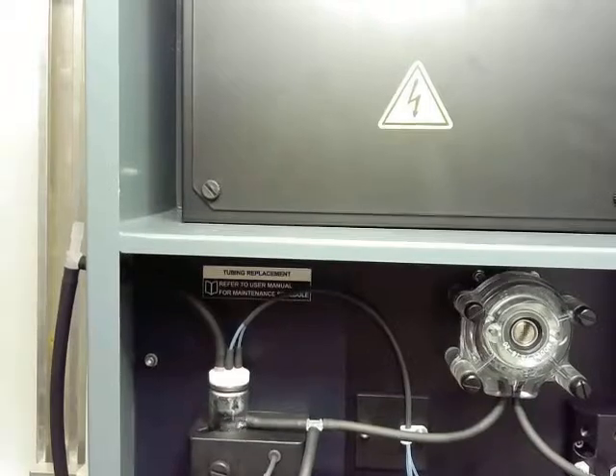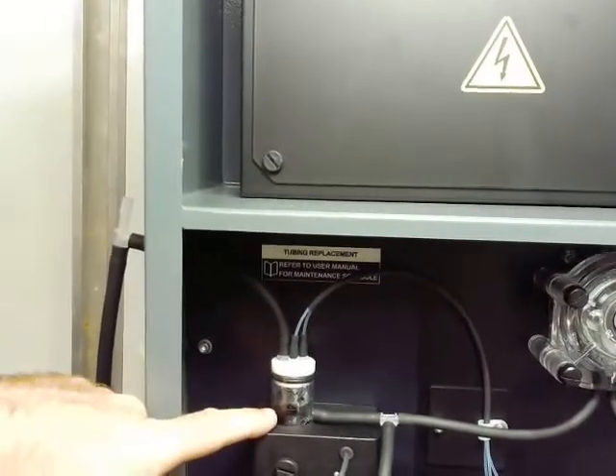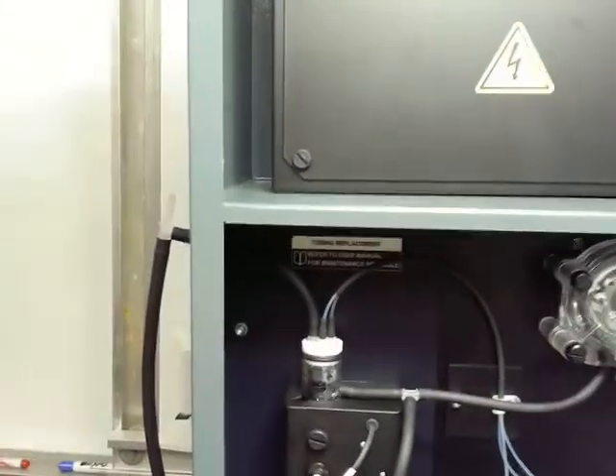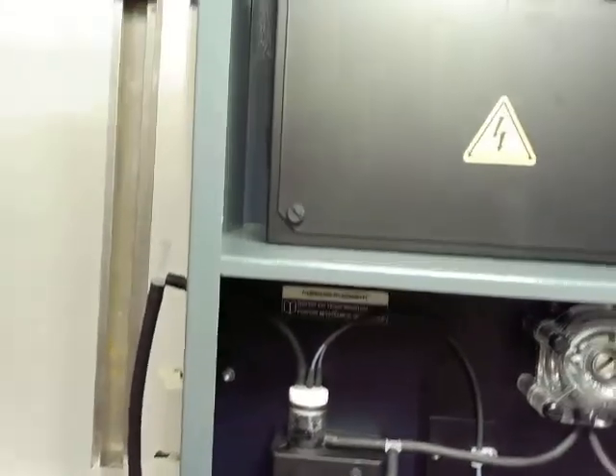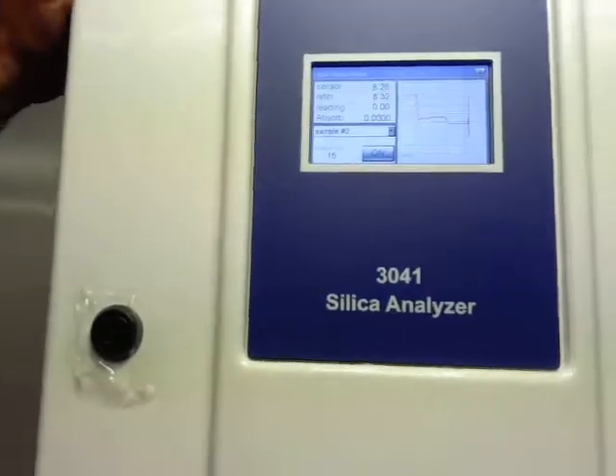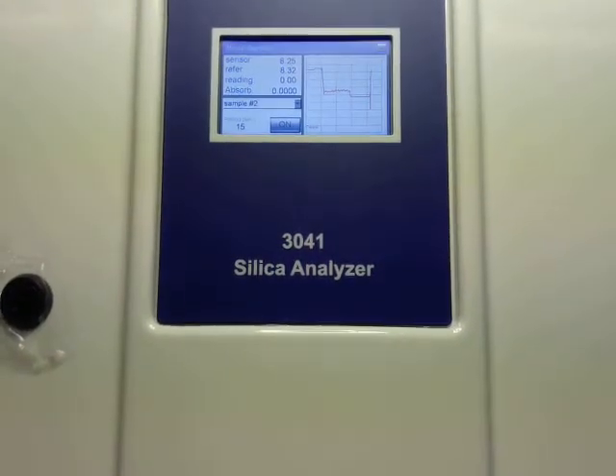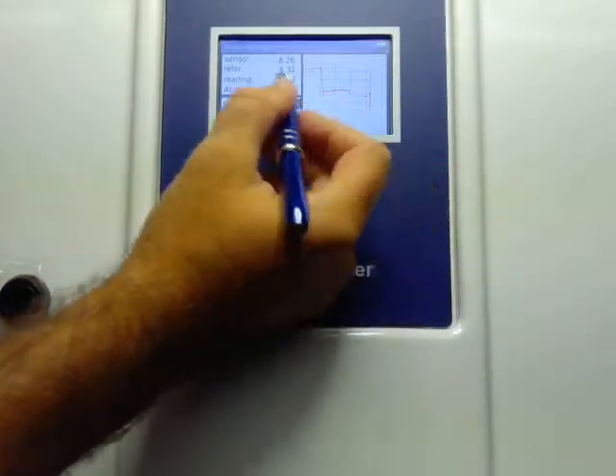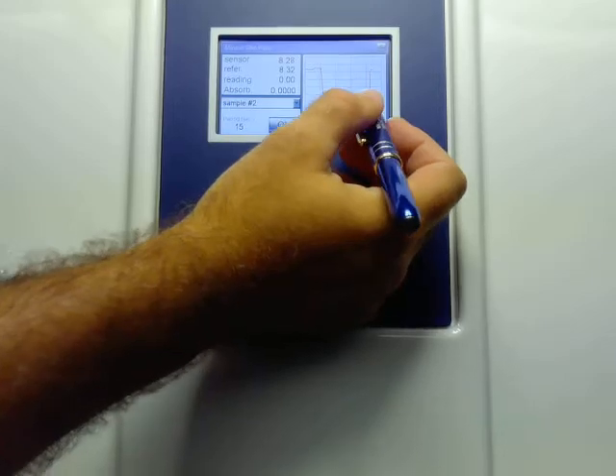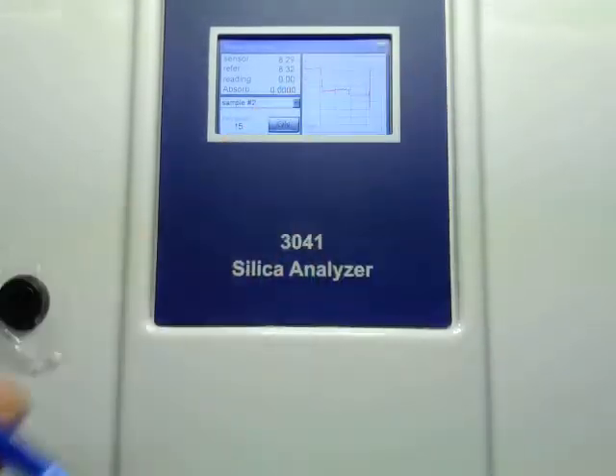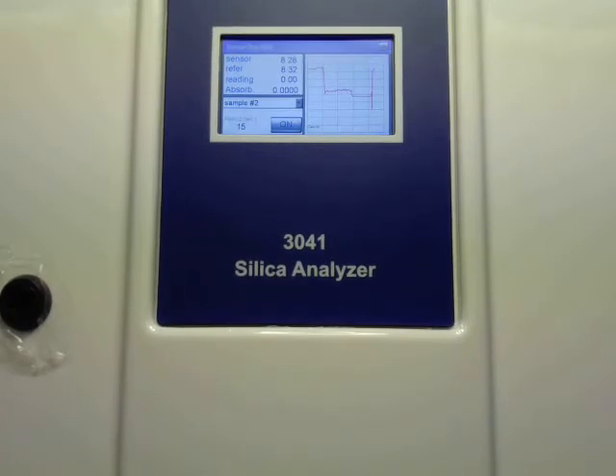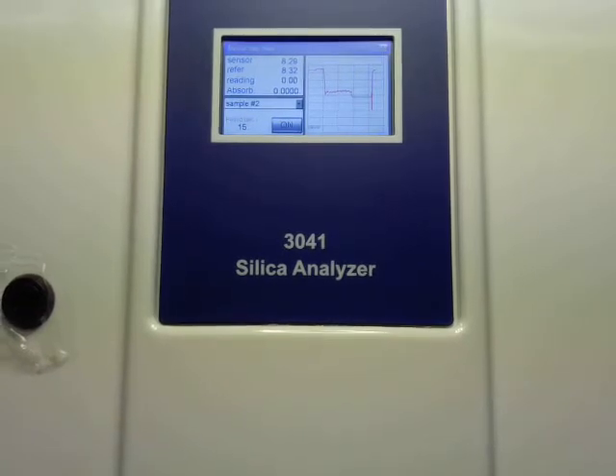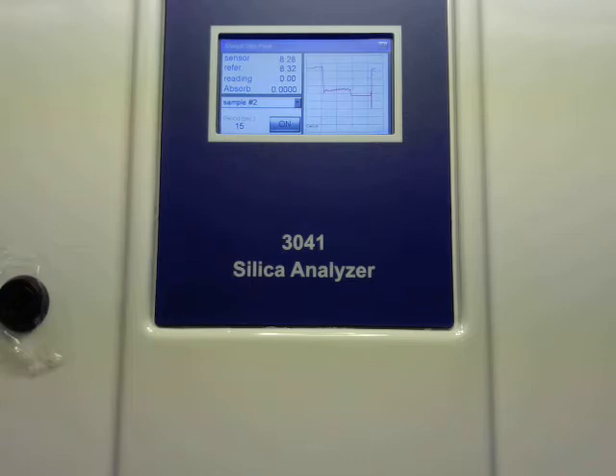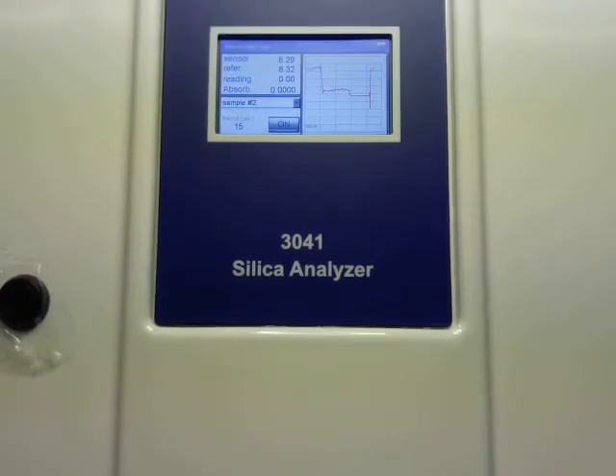Our sample pump's moving. We can see our sample getting drawn into our flow cell here, and it should start to fill up. Once the 15 seconds is over, it'll stop and go back into the mode waiting for the next command. What you can also see here is that our sensor value jumped up. Anytime the flow cell empties, our sensor value will drop down to about 4 or so. Anytime there's sample or standard in the flow cell, generally the sensor value is going to be around 9 or so. That number doesn't necessarily have to be exact, because every time it takes a reading, it rechecks that number for a new start point. But now we can go ahead and prime our reagent lines.